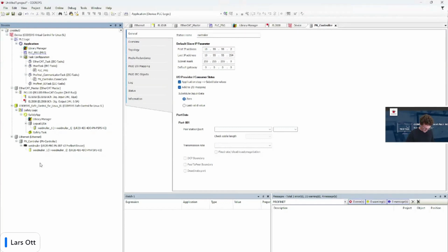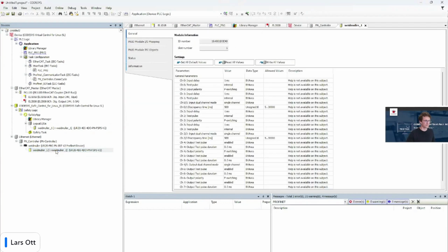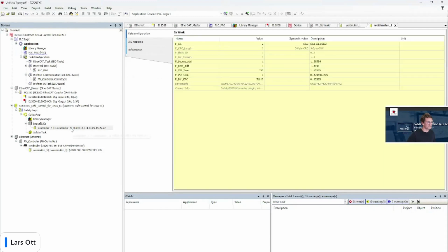So now we can start by configuring the non-safe side. In here you have various options on how the safety inputs verify their connectedness. And in this case, I'm gonna have these test pulses set up to be on the aux channels. And I think that's making sure you didn't crosswire the safety inputs and are reading the wrong one by accident. Yeah, we've done that.